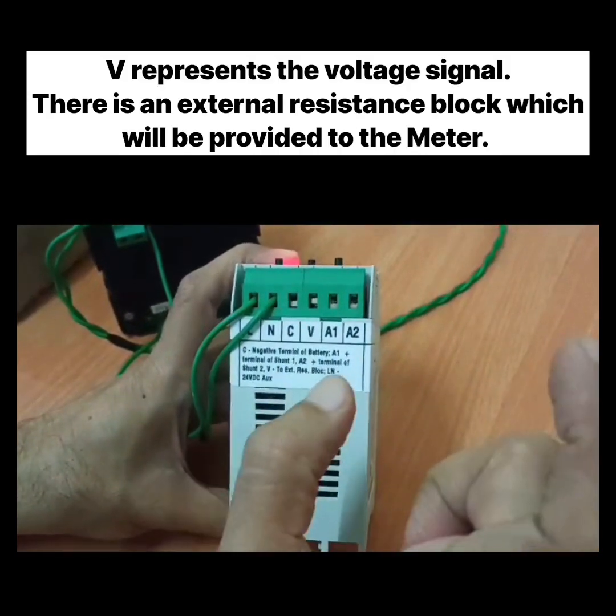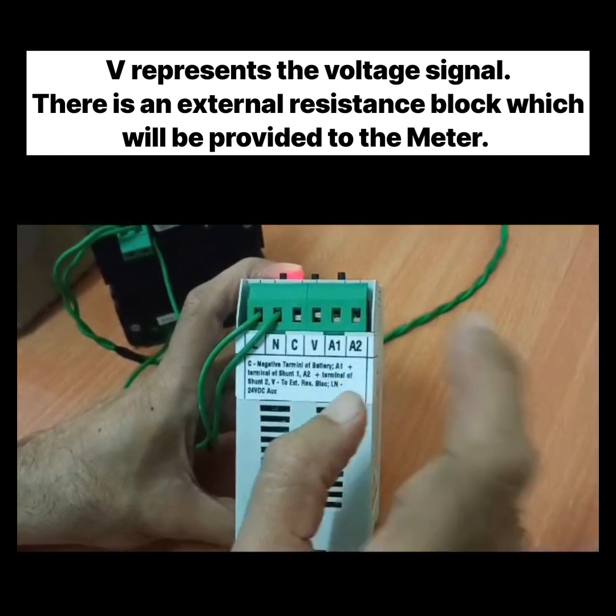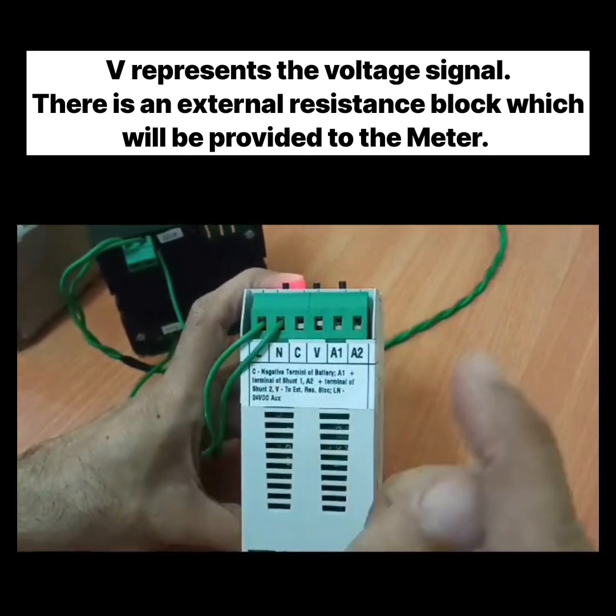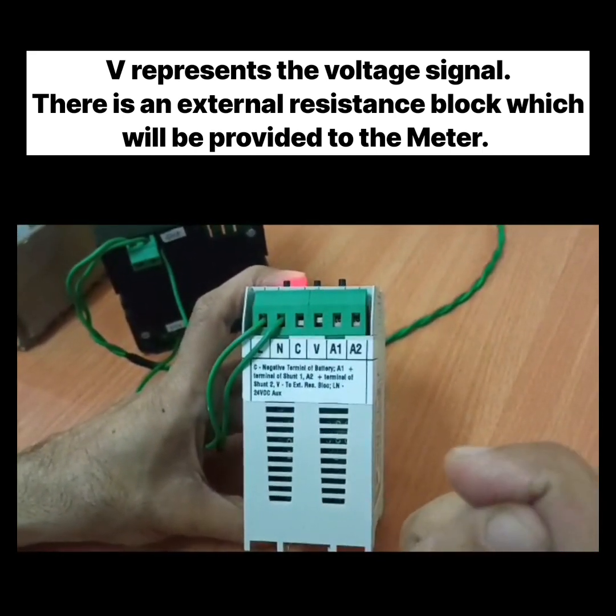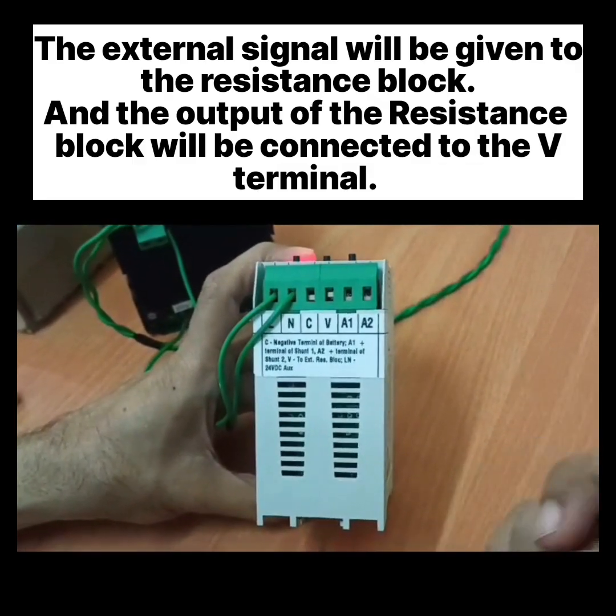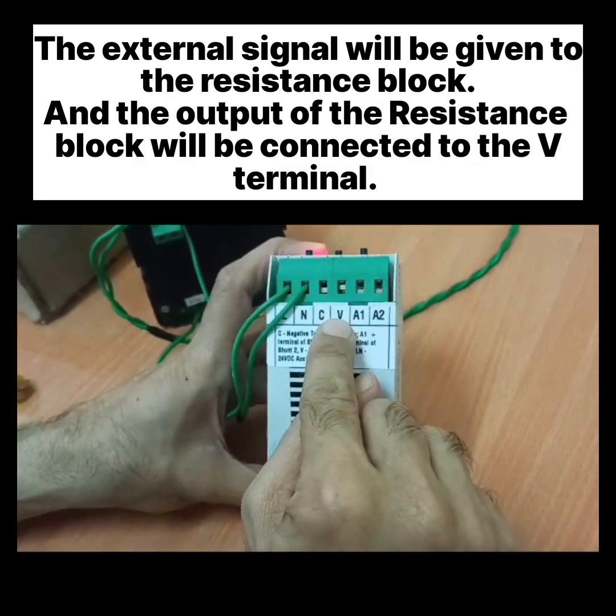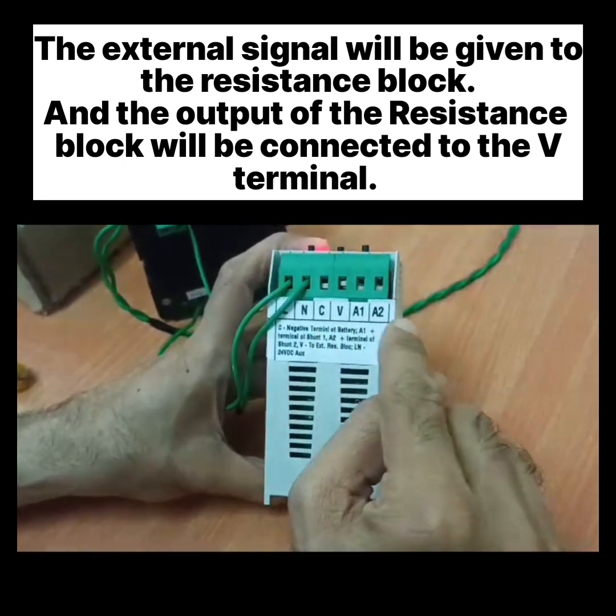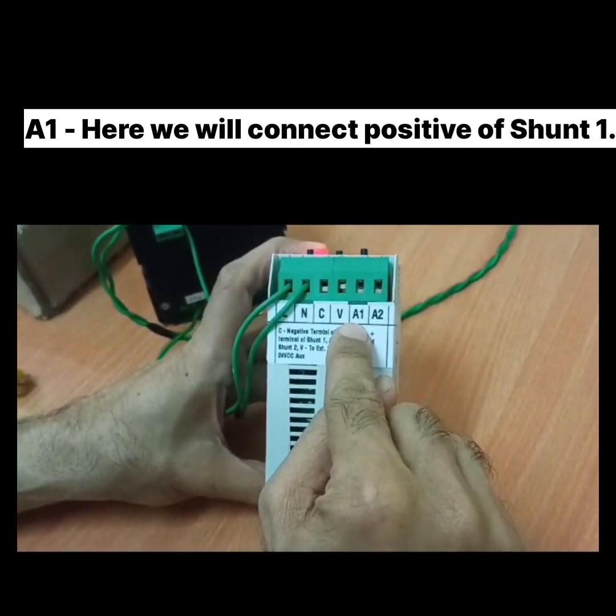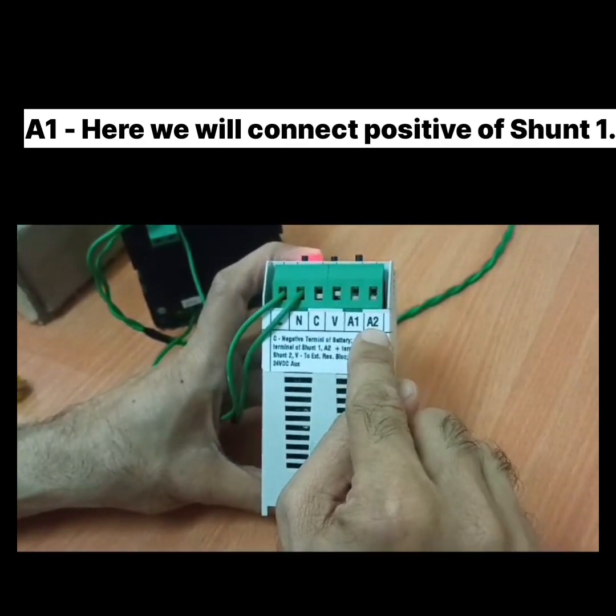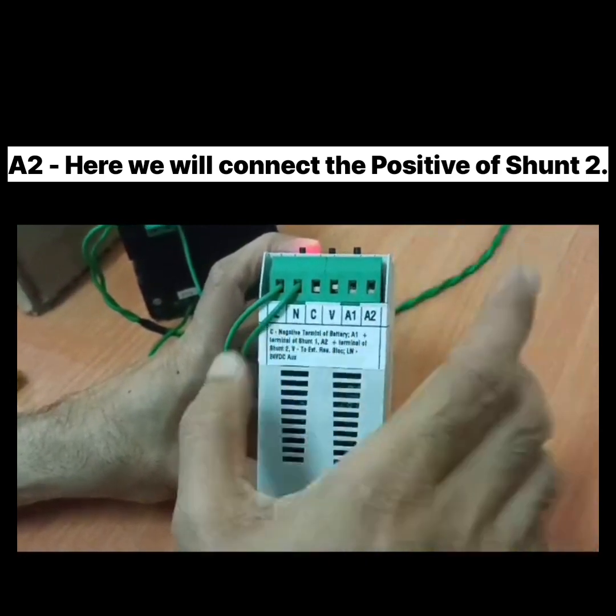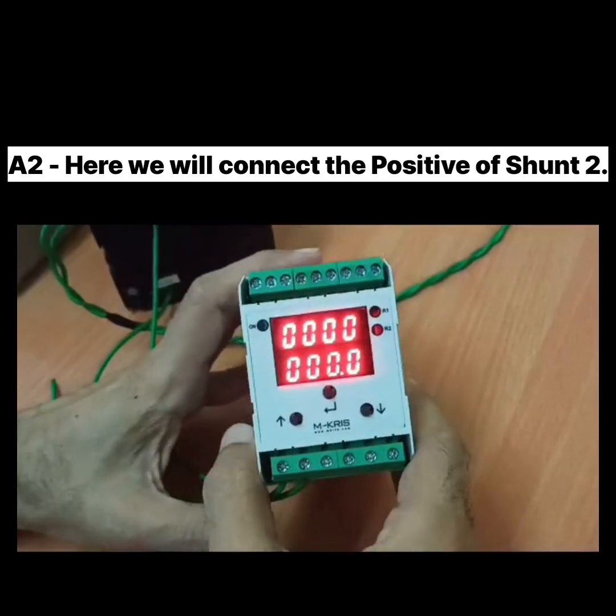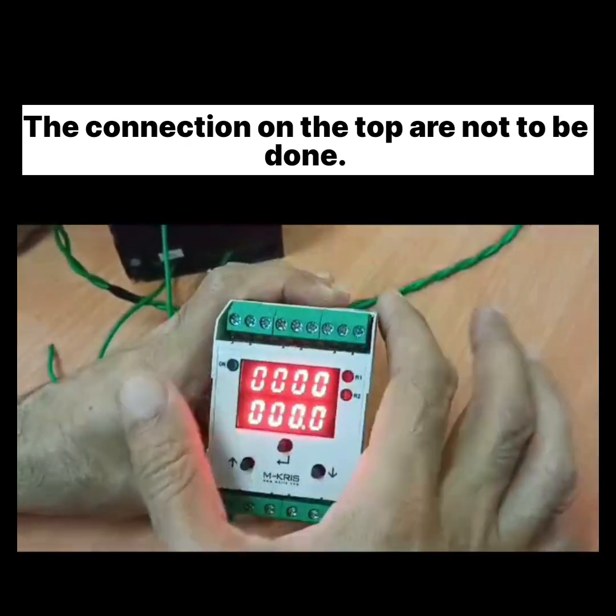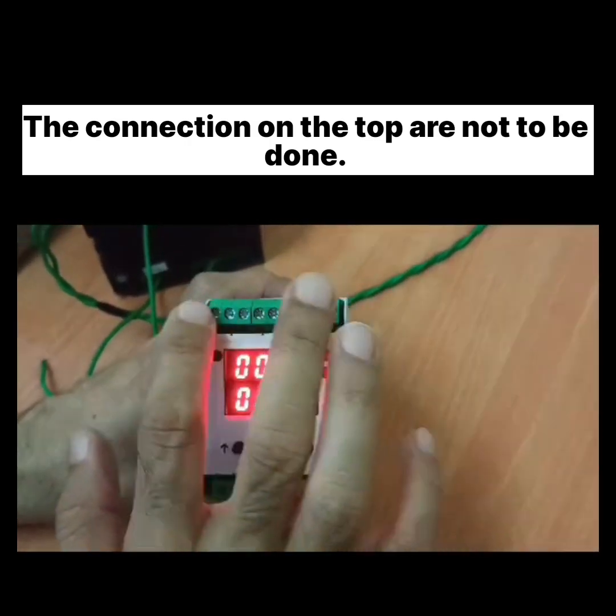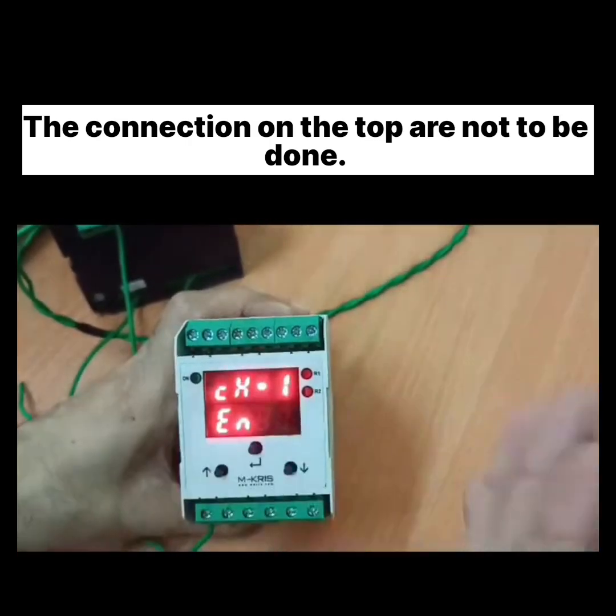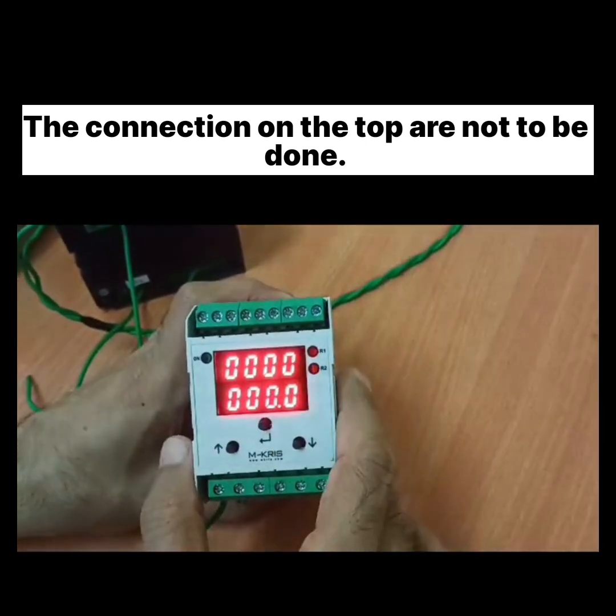There is an external resistance block which will be provided with the meter. The external signal will be given to the resistance block, and the output of the resistance block will be connected to the V terminal. Here we will connect the positive of shunt 1, here the positive of shunt 2. The connections on the top are not to be done. There are no connections going inside here.